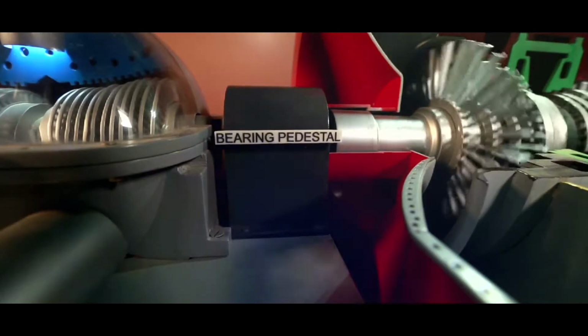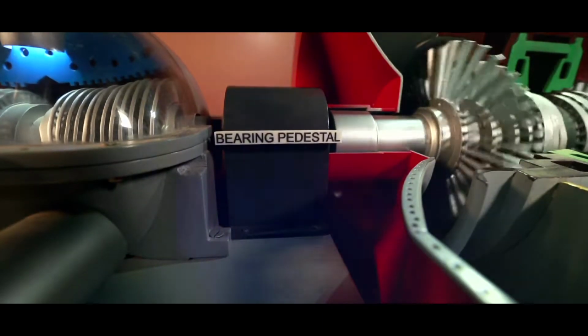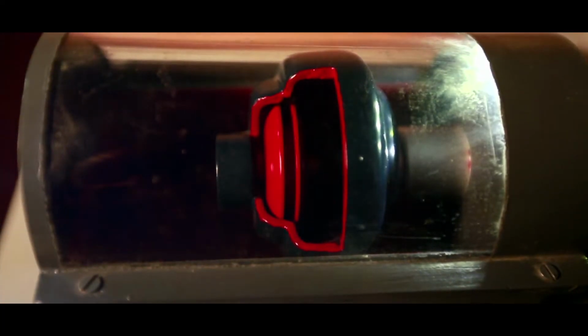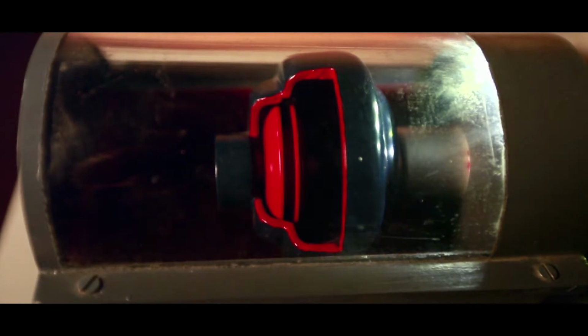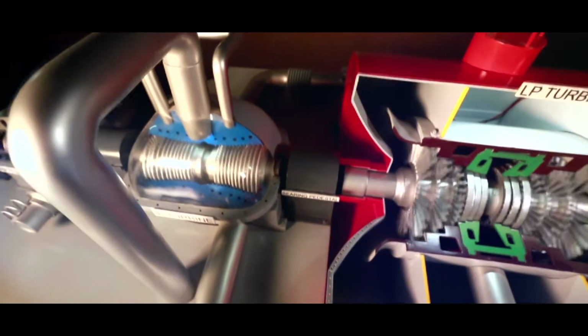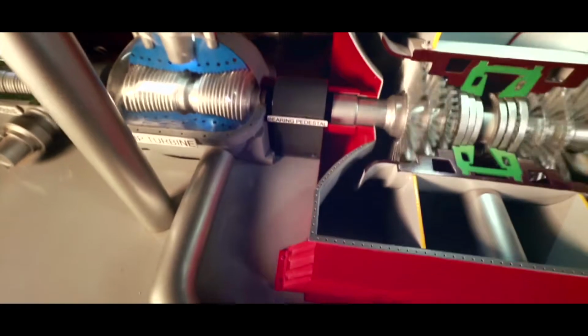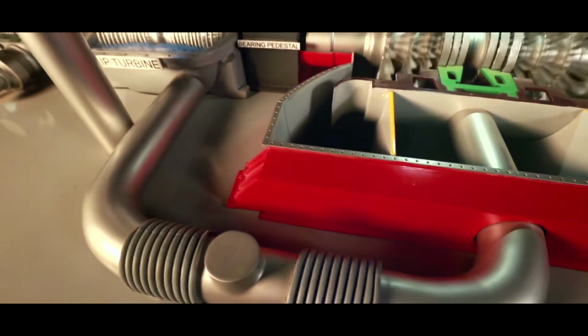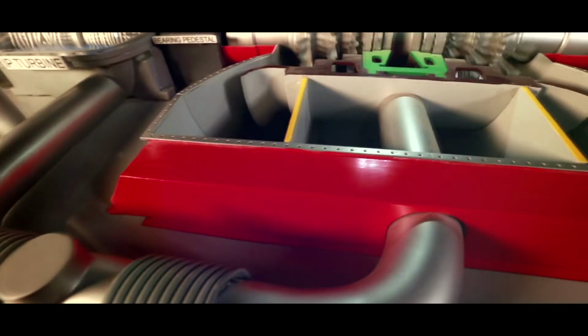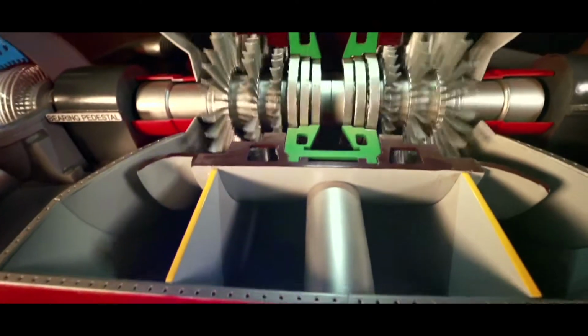This three-part construction is supported at various intervals on bearings, ensuring as frictionless rotation of the central shaft as possible. These journal bearings consist of an upper and lower shell. In order to prevent the bearing from exerting a bending pressure on the rotor, it is pivot mounted in a spherical support.